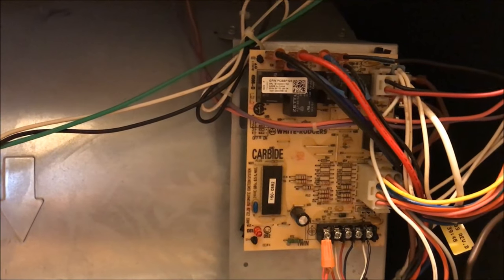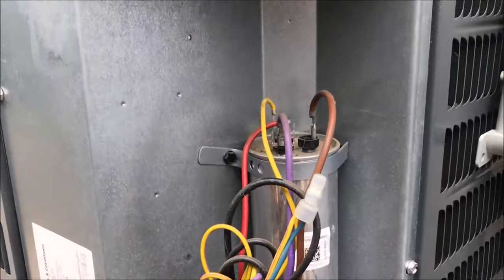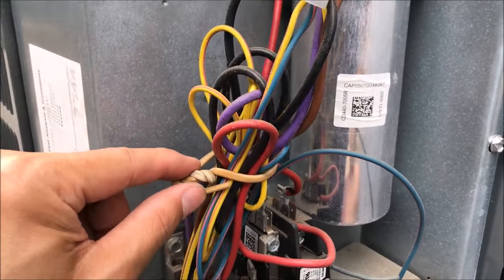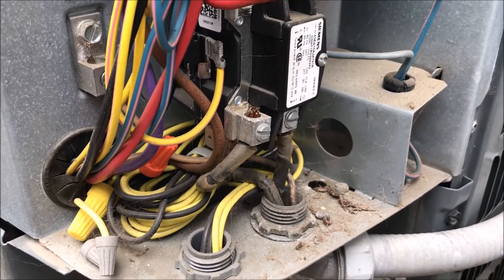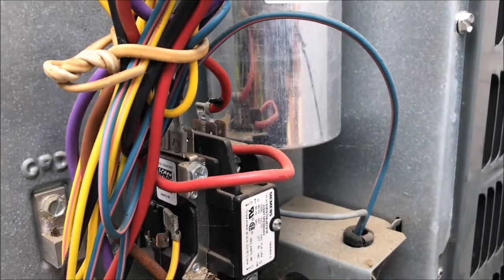I think the problem might be a contactor coil, or some wire got cut or shorted. Let's go outside. Here I am at the condenser. I took the liberty of removing the cover that protects the electrical wires and other components. As recommended, I checked the wires to see if anything was cut, crossed, or touching each other to cause the fuse to blow — but nothing was wrong there. I also checked the contactor unit.